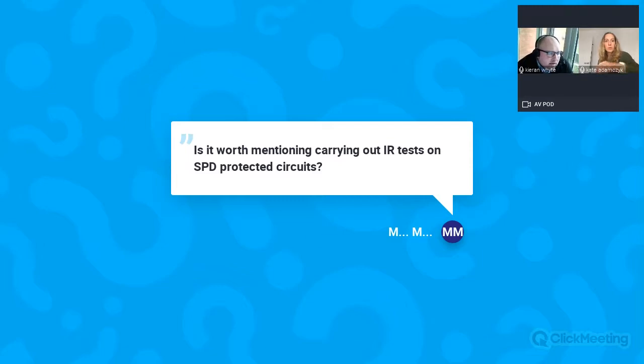So when we do dead testing, such as insulation resistance tests, it should always be done on the outgoing circuits. It's only when we go to the live tests, where you test the tripping time of the RCDs and check the Zs, that it will be connected. So yes, good point. All electronic devices should be removed before IR testing.